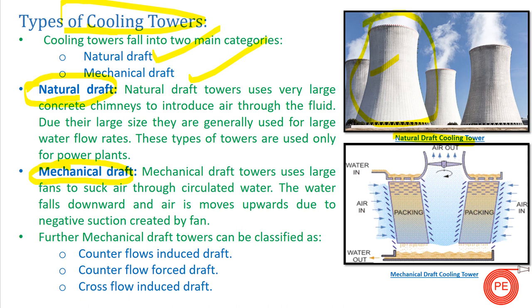Mechanical draft cooling towers are found extensively in pharma, steel, and many power plant industries. The basic difference between natural draft and mechanical draft is that in mechanical draft, a fan is installed — either at the top or bottom — to introduce air inside the cooling tower. In natural draft, no fan is installed; cooling is done by natural means, and the tower height is calculated to achieve the desired inlet and outlet temperatures.